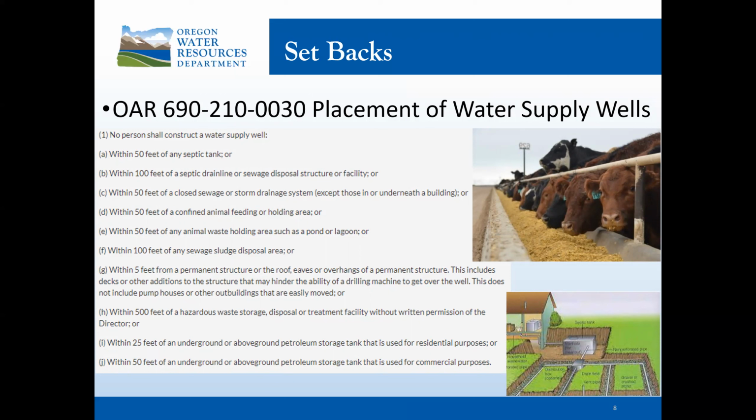No person shall construct a water supply well within 50 feet of a septic tank, within 100 feet of a septic drain line, within 50 feet of a closed sewage or storm drain system, within 50 feet of a confined animal feeding lot, within 50 feet of an animal waste holding area, within 100 feet of a sewage lagoon or sewage disposal area, and within 5 feet of a permanent structure, eaves, or overhangs of a building.